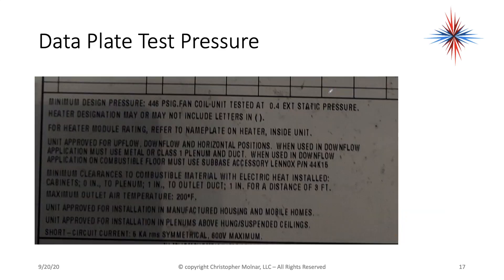Then we compare that to the data plate where there's a test static pressure rating, which is your design static pressure for the unit. This unit is rated at 0.4, so my static pressure of 0.62 is too high.